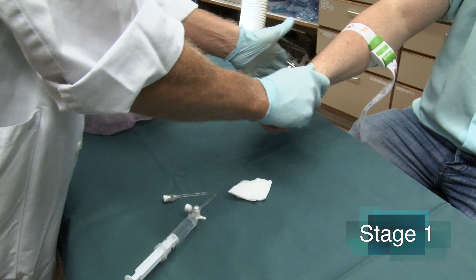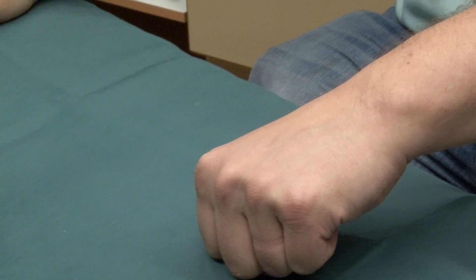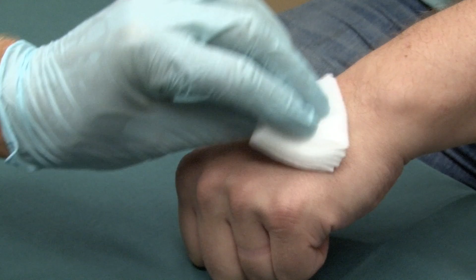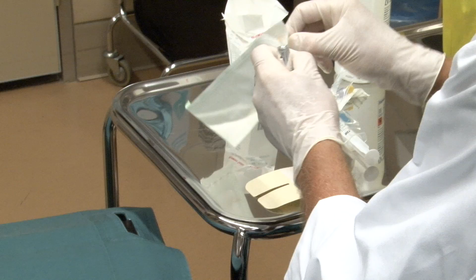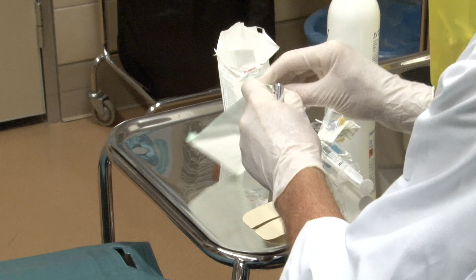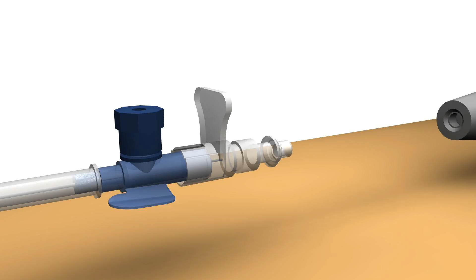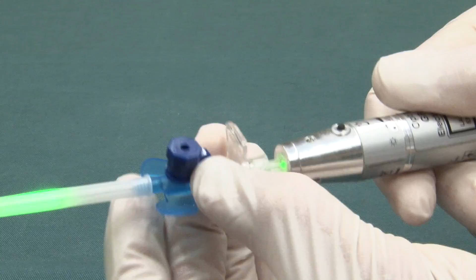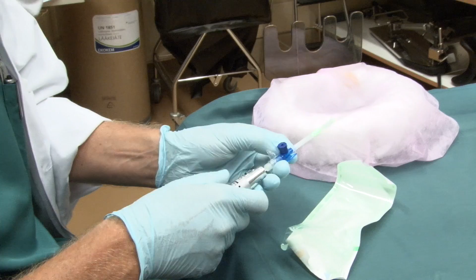Select the cannulation site and prepare it in accordance with institutional standard operating procedures. Remove the OptiVein IV catheter from its single-use blister packaging. Mount the catheter onto the OptiVein electronic unit and press the on-off button to activate the light. The green light illumination of the protective cap and adapter will appear.